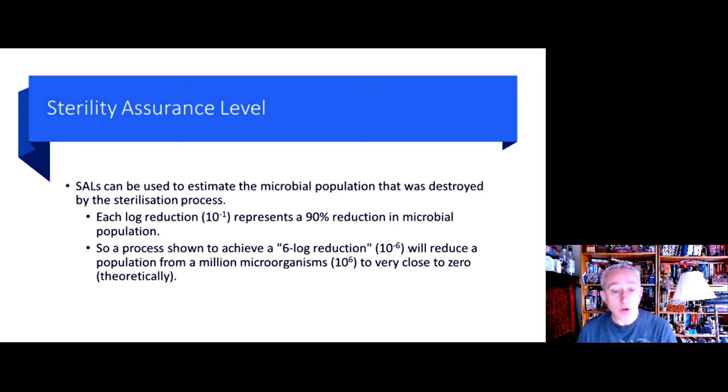With the sterility assurance level, it can be used to estimate the microbial population that was theoretically destroyed by the sterilization process. We can assess this because microorganisms are destroyed in a linear manner. We know that each logarithmic reduction represents a 90% reduction of the microbial population. So when we define sterility or sterilization as achieving a 6 log reduction, then this is what we're using to describe the elimination of a million microorganisms to a value close to zero theoretically.